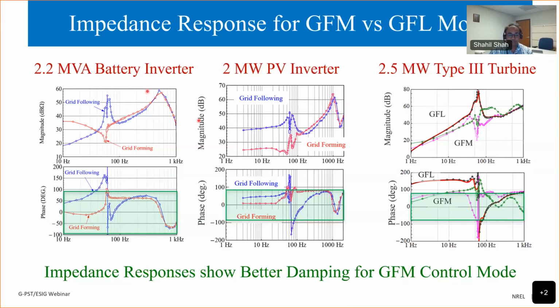So here are impedance responses of a real 2.2 MVA battery inverter, a 2 megawatt PV inverter, and a 2.5 megawatt type 3 turbine. The impedance responses shown are basically positive sequence impedance responses, when these devices are operated either in grid forming mode versus grid following mode. And as you can see, within the control bandwidth below a couple hundred hertz, the impedance responses are different because they are dominated by the controls inserted in the device. At a high frequency, it's mainly about filters and transformers, so the impedance doesn't change with the control mode.